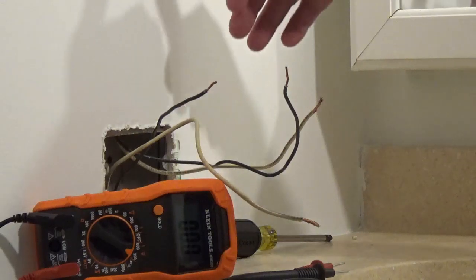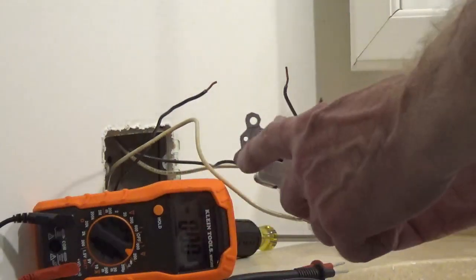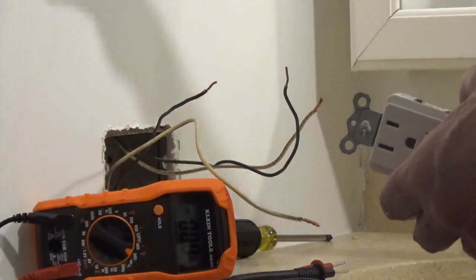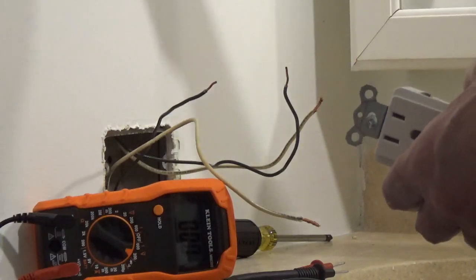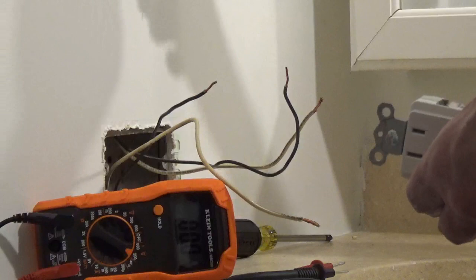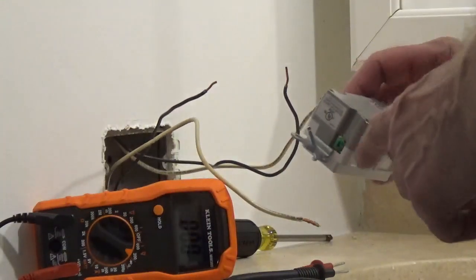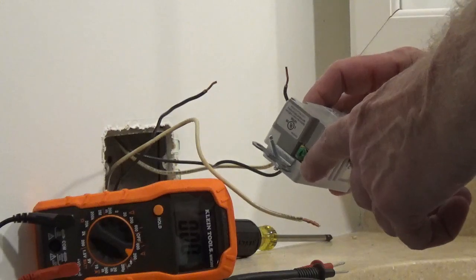When I put the metal screw and the metal strap on the GFCI into this metal box, it's grounded all the way back to the service panel. If you're in an area with non-metallic cable, you're going to have a bare ground wire that you'll be connecting to the green ground screw.